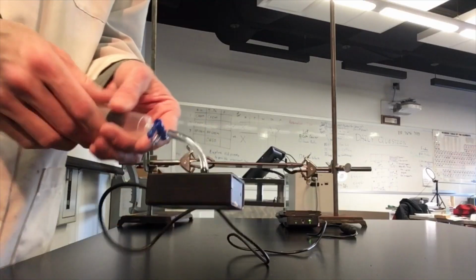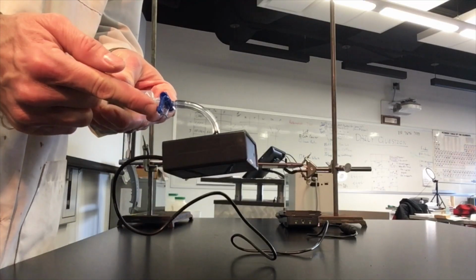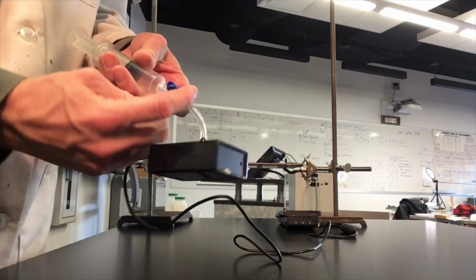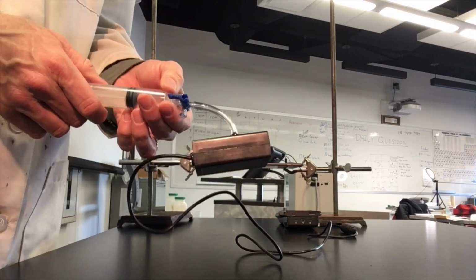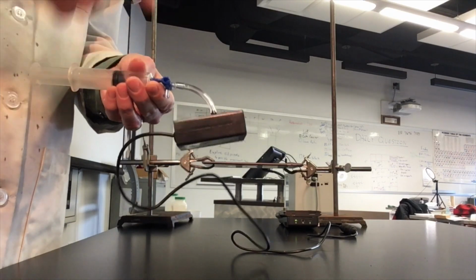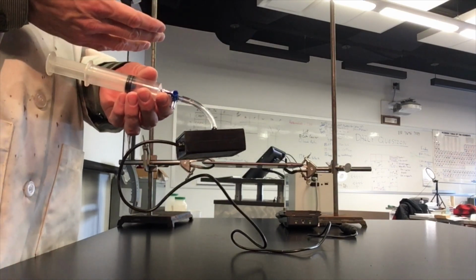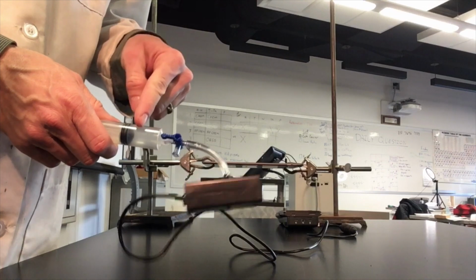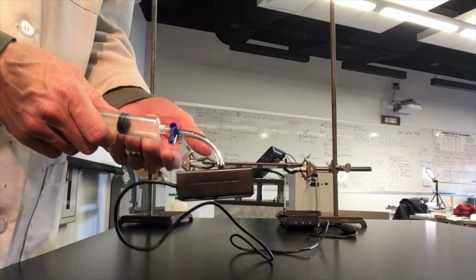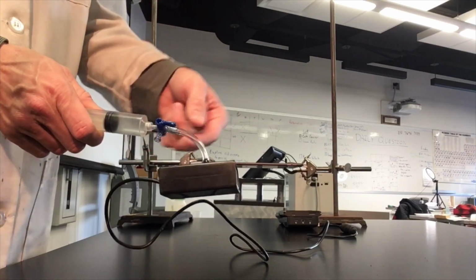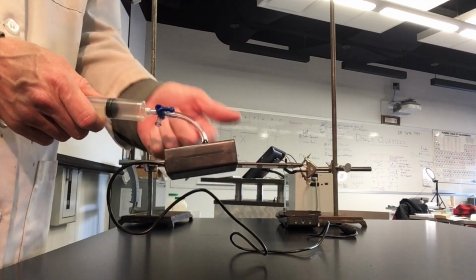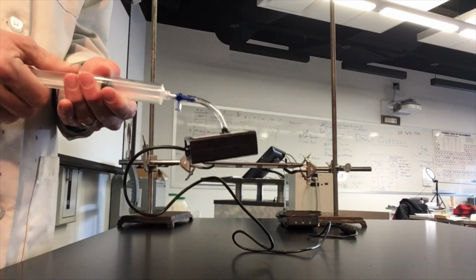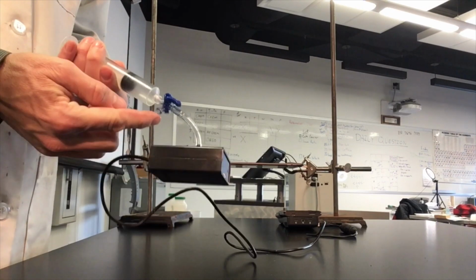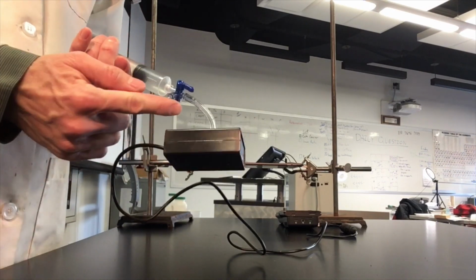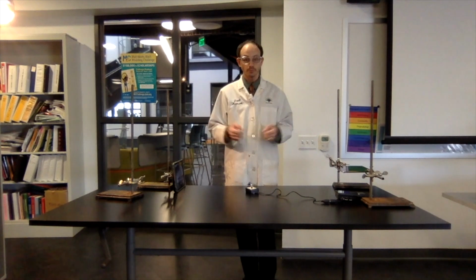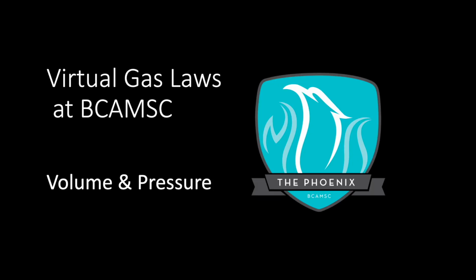Now, on the pressure sensor, there's a gauge that I can point at one of 3 different locations. Wherever this gauge is pointing, that is what is closed. So, right now the syringe would be closed. If I moved it down here, it's closed to open air. And if I move it this way, it's closed to the actual pressure sensor itself. So I could move this all I want, and all it's doing is sucking air in and out of that hole that's right there. Cool. Now we're ready to start our experiments.